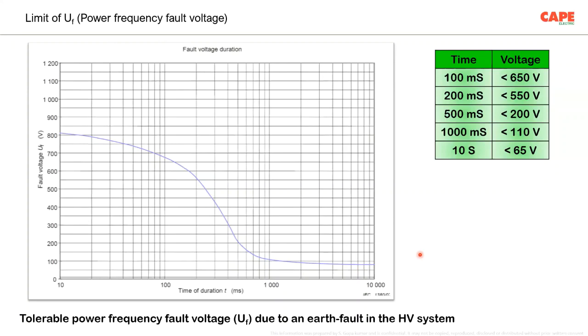IS 732, you can look at this particular picture. What it says is, against shock, the first safety measure is that the shock voltage within the installation, where people are living, where people are working, must be reduced to less than this particular limit. You can see on the x-axis the duration of the fault, and on the y-axis the fault voltage. Fault voltage, say for example, 800 volt, 10 milliseconds. About 100 milliseconds, it's a little bit less than 700 volt. Now you see this particular graph, the blue color line. I don't know whether it's clear to you or not. Probably it's clear.